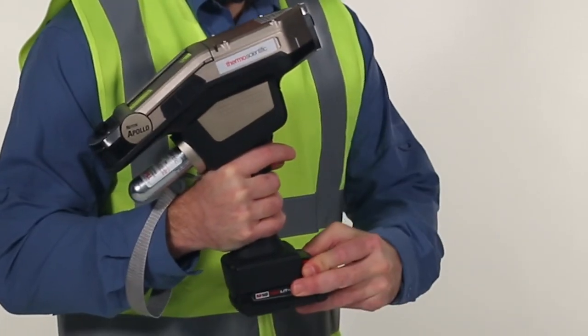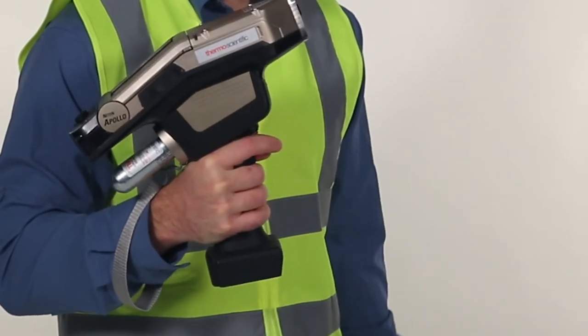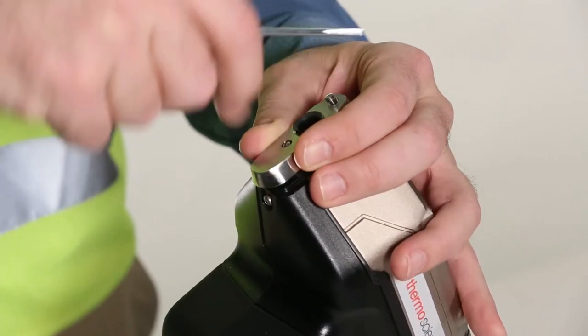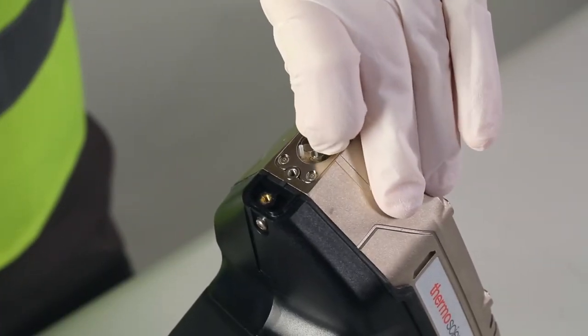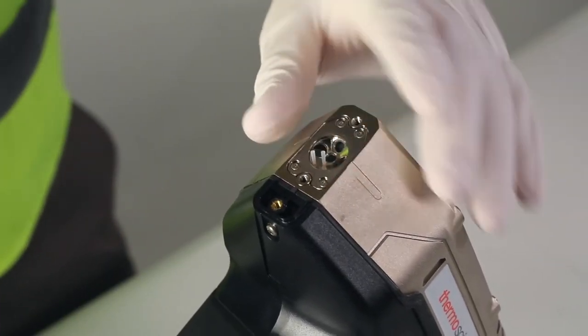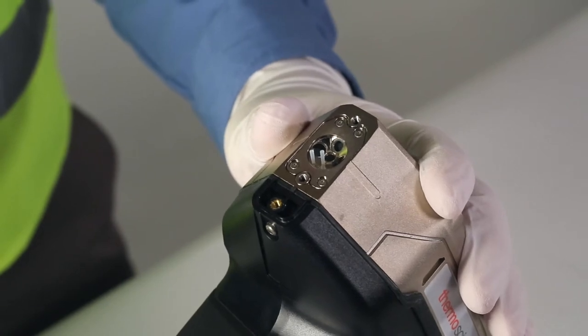Proceed by removing the battery pack from the base of the analyzer. Use a flathead screwdriver to remove the metal nose piece on the front of the instrument. Prevent any cleaning mixture from entering the analyzer by using the provided argon port plugs to seal the argon ports.